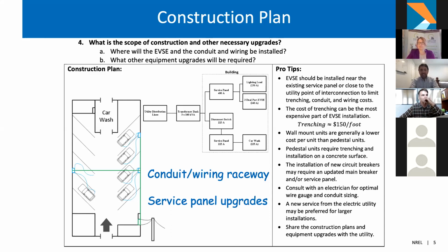Sure, yeah. So that came up in this particular site assessment. We touched on it in the previous portion of the session. This service panel in the top right here had about a 150 amp lighting load. When we looked through that, we realized the majority of that load was for the lights throughout the entire garage, so when most of the lights were on during typical operations, the majority of those circuits were occupied.